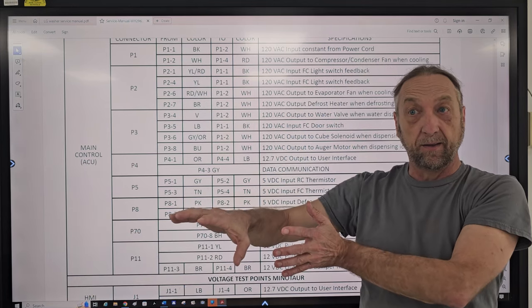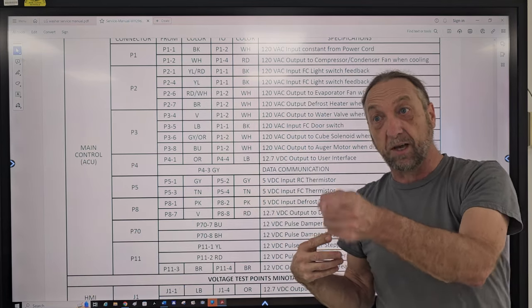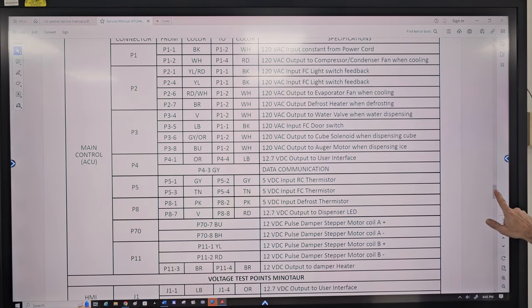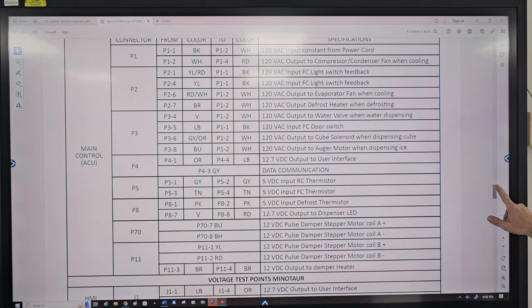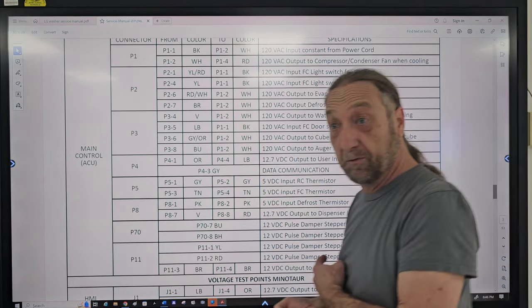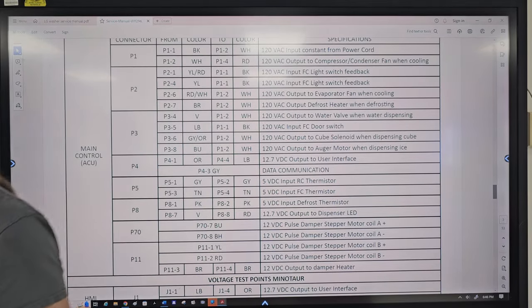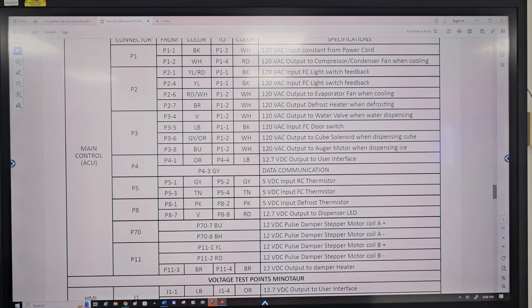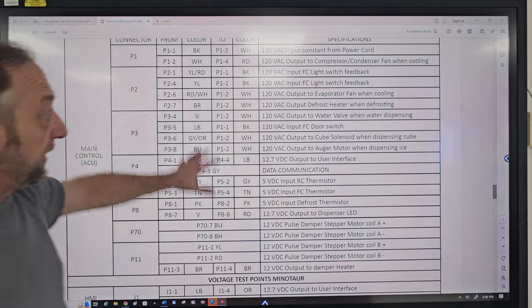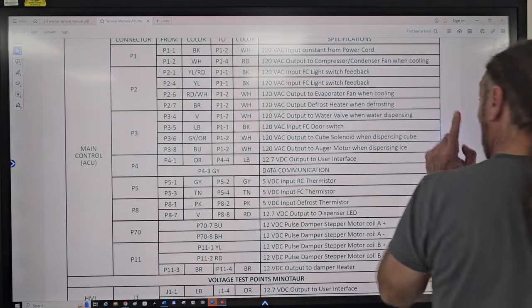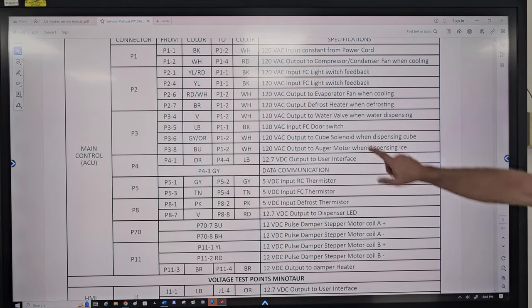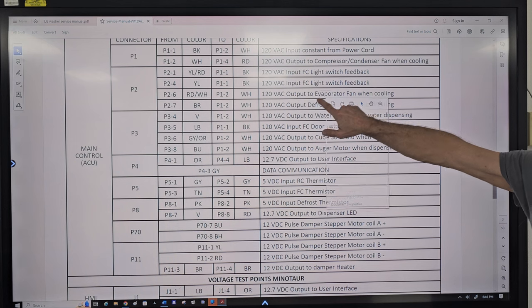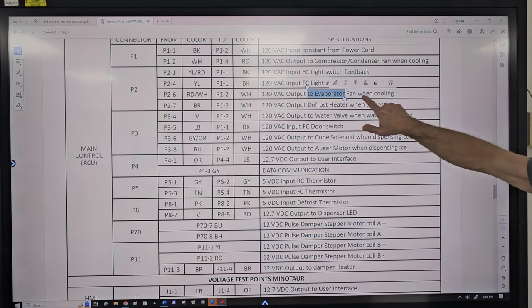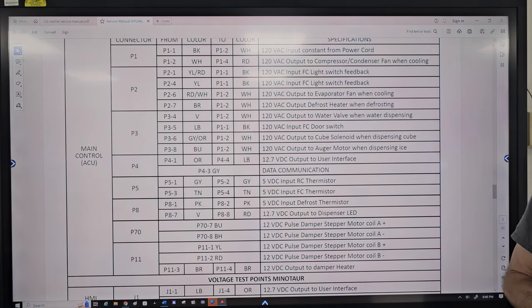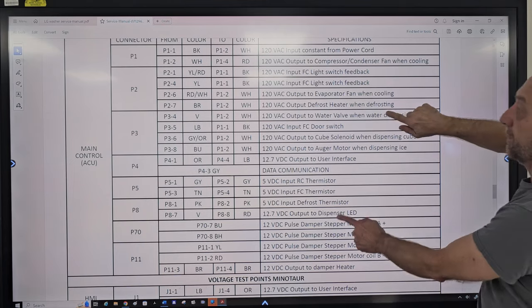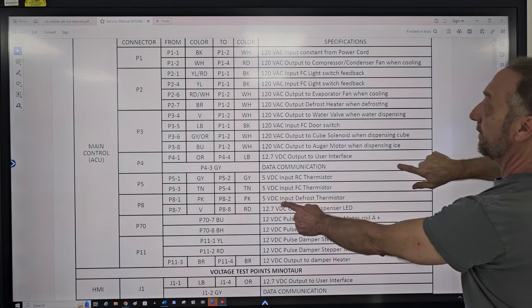We're worried about the fan. But the board part you said was correct - if we went to the board, we want to check if it's sending power to the fan, since our fan's not working. So on this page, where does it tell you about the fan motor? Right here: 120 volt output to evaporator fan when cooling.